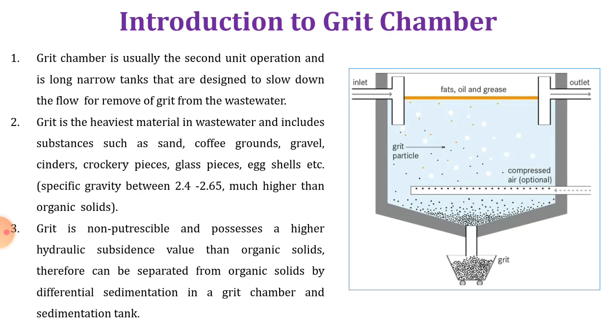The specific gravity of grit is between 2.4 to 2.65, which is much higher than organic solids. Grit is non-putrescible and possesses a higher hydraulic subsidence value than organic solids. Therefore, it can be separated from organic solids by differential sedimentation in the grit chamber and sedimentation tank. Being non-organic matter, it will not decompose easily and can be readily settled at the bottom and removed from the wastewater.